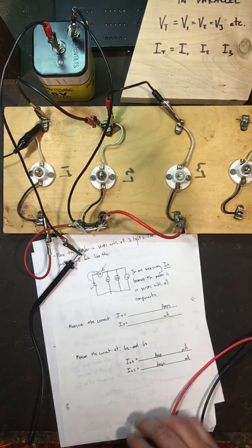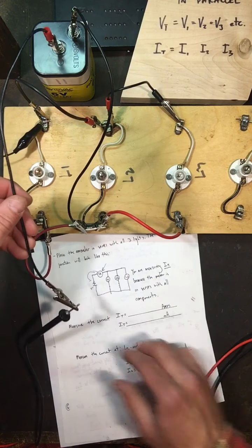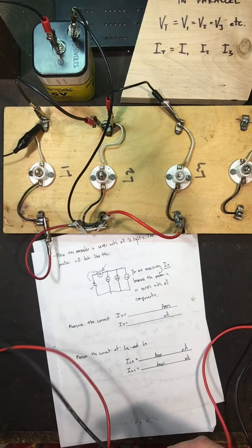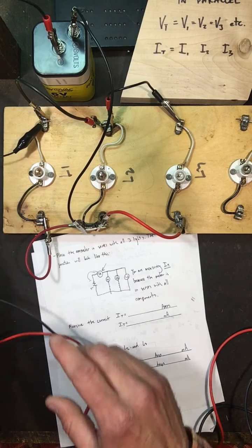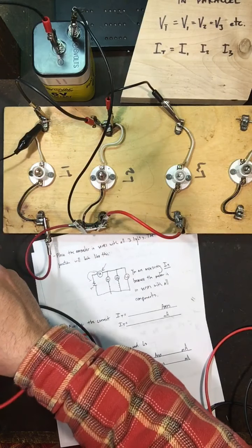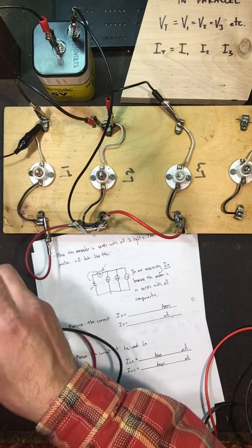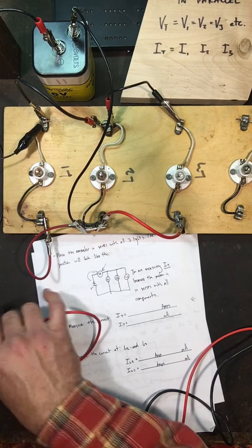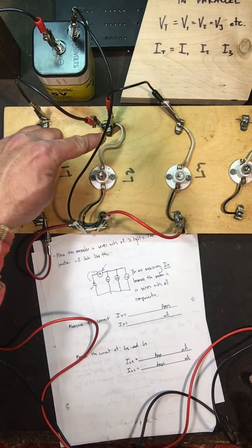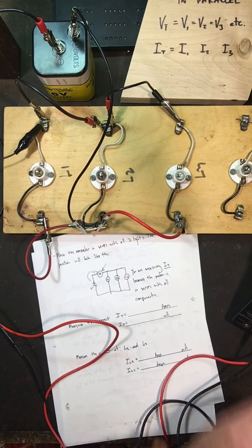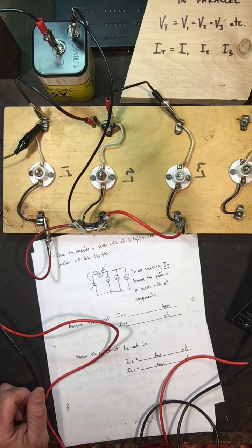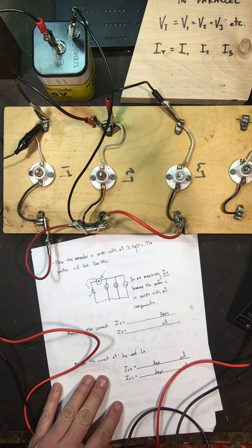The lights are on, but it should be brighter than that. So our negative, again, comes out to the negative side of the ammeter. We're in amps, direct current, from the negative side, goes through the ammeter, over to the positive side of the ammeter, and then to L1, L2, and L3. So I should be getting a number here. 3 milliamps. That is not correct.